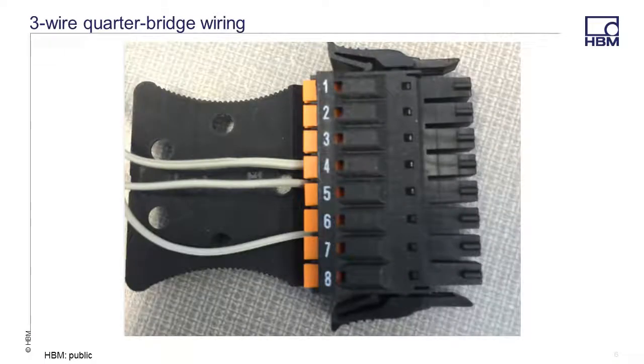Here is a close-up of the MX1615B connector with a three wire strain gauge connection. In the previous slide, it showed that pin 8 was for cable shield, but since this cable is unshielded, there is no connection. There is also no TEDS connection. The TEDS and shield are optional connections.